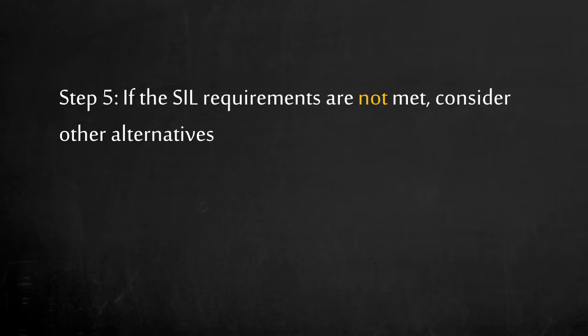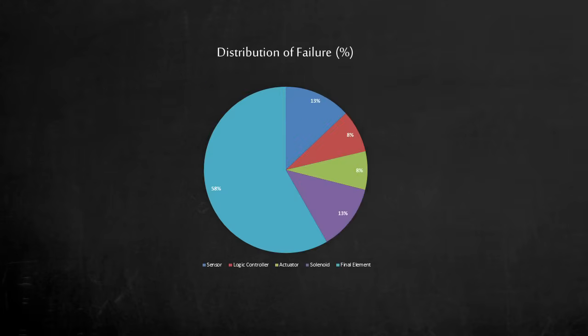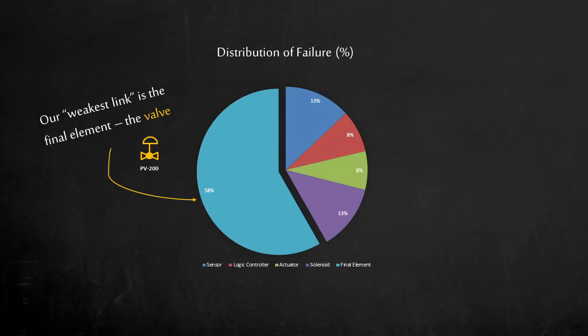Step 5. If you cannot meet the safety integrity level requirements, which is what we've encountered here, you can consider how to improve the reliability of your safety instrumented function. How can we approach this? Let's take a look at the distribution of failure in our current setup. We want to focus on the weakest element first. Now you can see clearly a picture of the weakest link in this safety function. Our weakest link is the final element. Our valve is contributing 58% of the total failure.